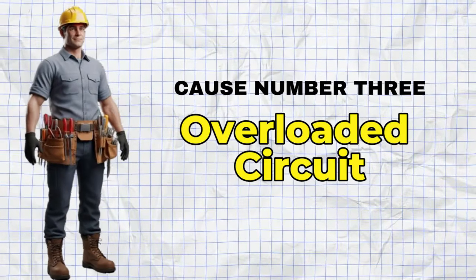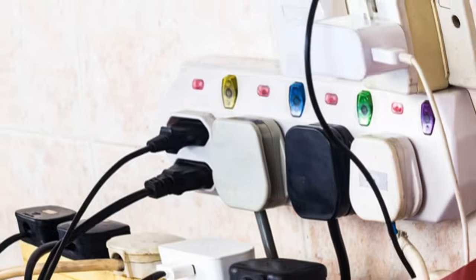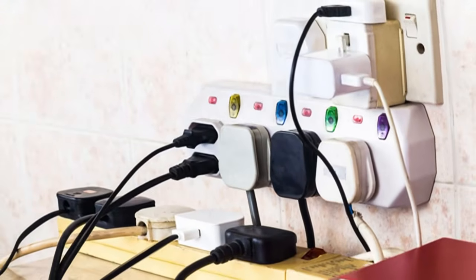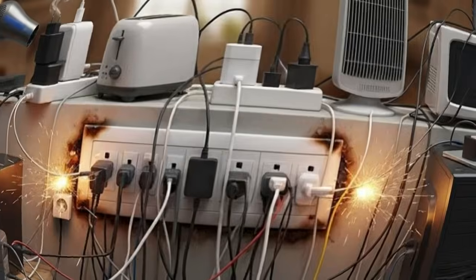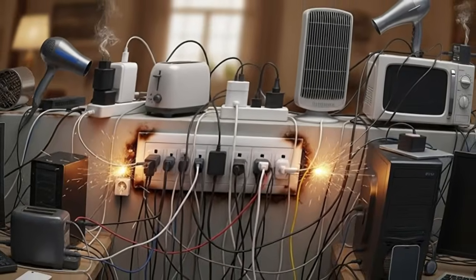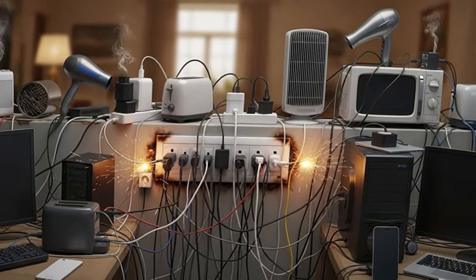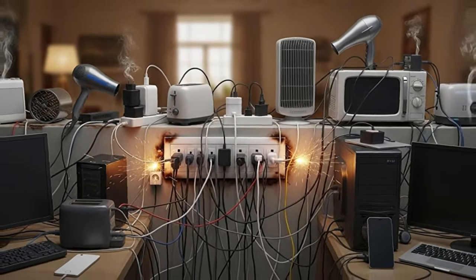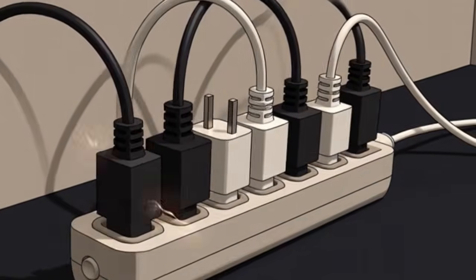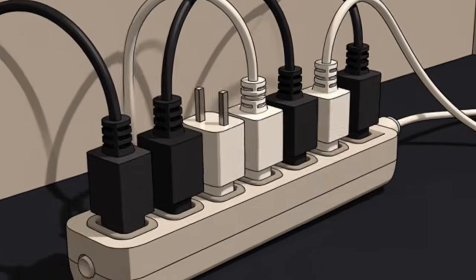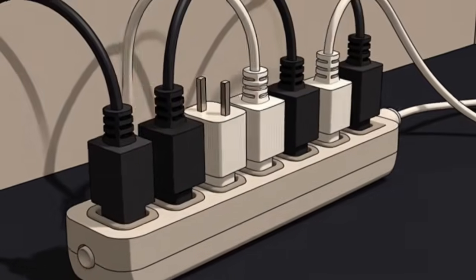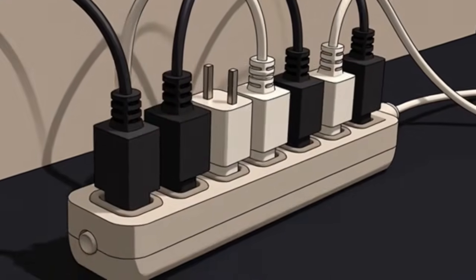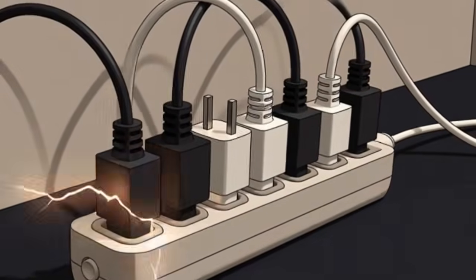An overloaded circuit is different from a short circuit or ground fault, and it behaves differently too. An overload occurs when you draw more current through a circuit than the wires and breaker are rated to handle. Too many devices plugged into one circuit. A space heater running alongside a hairdryer. Multiple appliances operating simultaneously on a circuit designed for lighter loads.